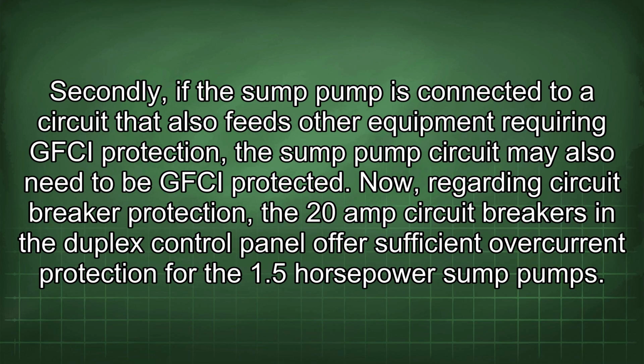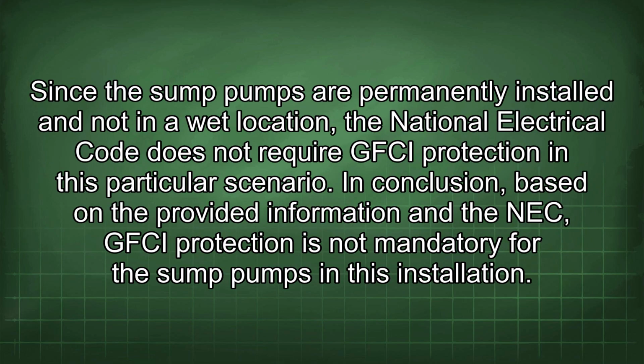Now, regarding circuit breaker protection, the 20 amp circuit breakers in the duplex control panel offer sufficient overcurrent protection for the 1.5 horsepower sump pumps. Since the sump pumps are permanently installed and not in a wet location, the National Electrical Code does not require GFCI protection in this particular scenario.